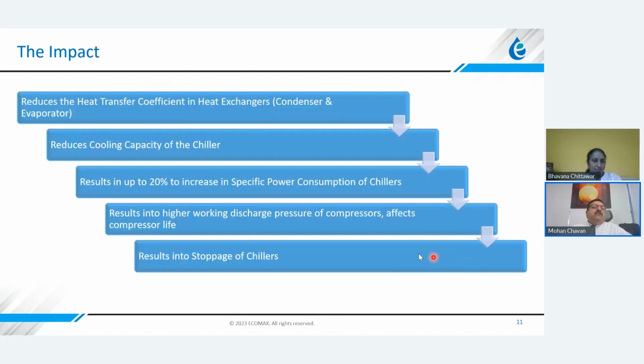If you look at the impact of scaling or fouling on the condenser or evaporator, the first impact is it reduces the heat transfer coefficient in the heat exchangers. The moment we have this, it will reduce the cooling capacity of the chillers, okay? So you don't get proper cooling. Suppose the chiller is designed for, say, 1000 TR, you may not get 1000 TR cooling if the condenser is fouled. And the specific power consumption increases by up to 20%. It depends on the extent of fouling and at what value the condenser approach is. Depending on that, you will have the potential to save here.